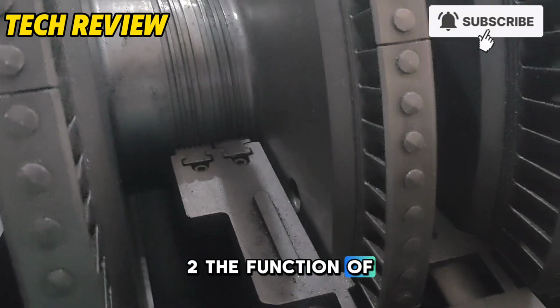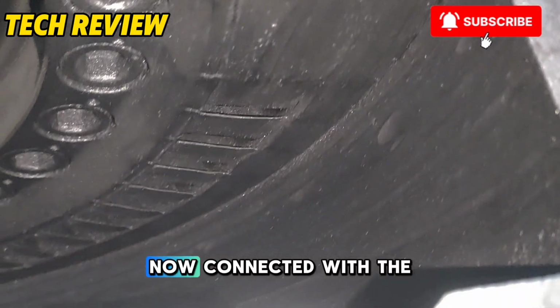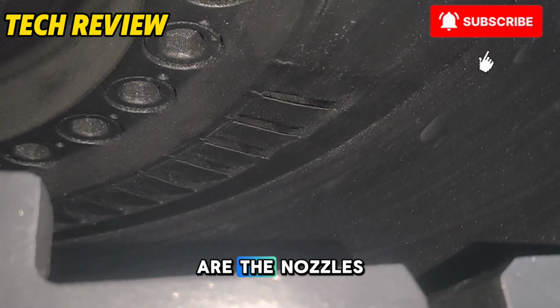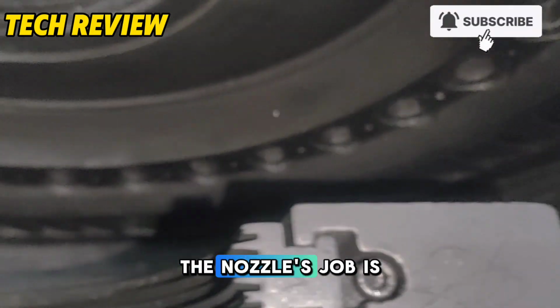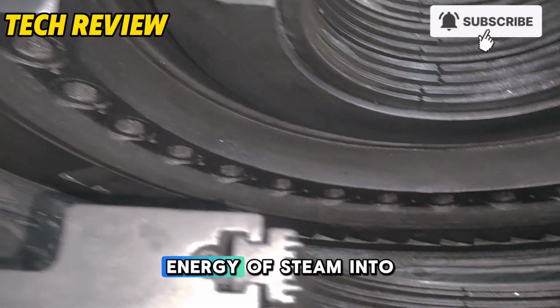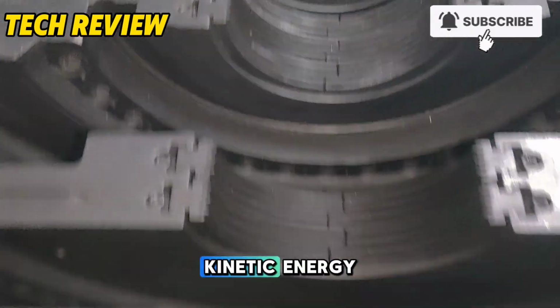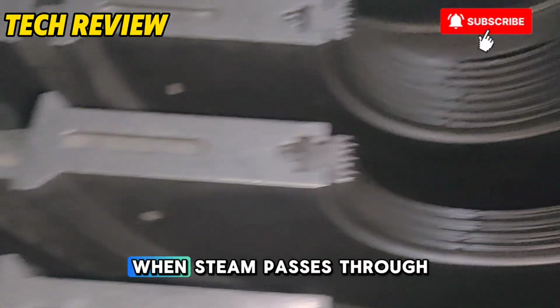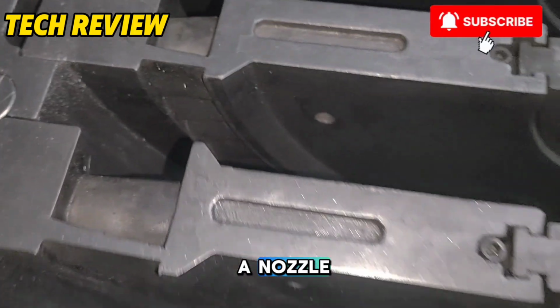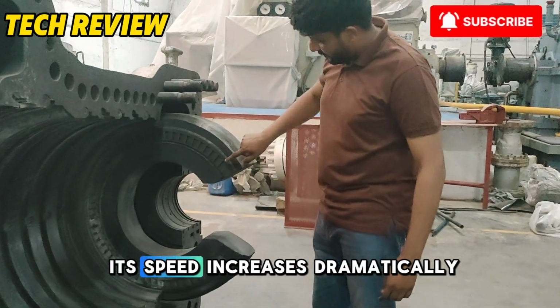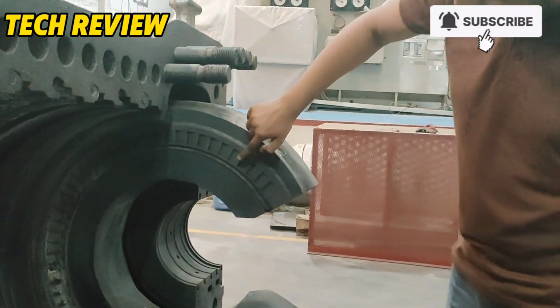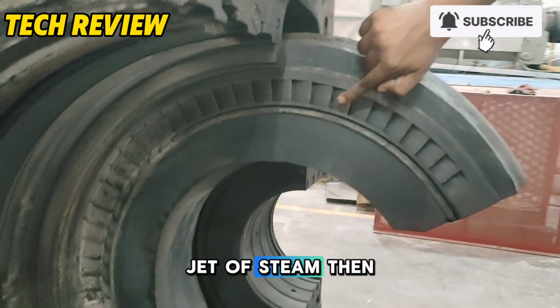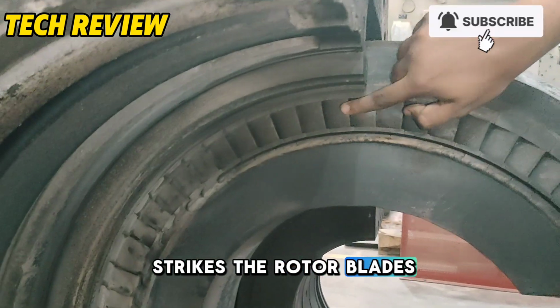2. The function of nozzles. Now, connected with the diaphragm are the nozzles. The nozzle's job is to convert pressure energy of steam into high-velocity kinetic energy. When steam passes through a nozzle, its pressure drops, but its speed increases dramatically. This high-speed jet of steam then strikes the rotor blades.